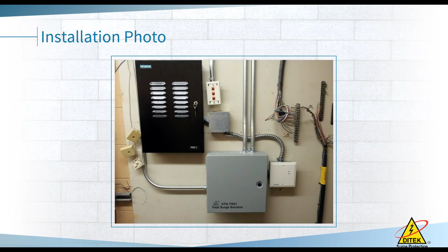I've done a number of site surveys where contractors have run a ground wire from a device like this, and let's say they came out to the left to where this bus bar is, and let's assume that bus bar is a wall. They hit that wall and they make a 90-degree sharp turn down to the bottom. They reference ground at the bottom at the floor. You don't want to make a 90-degree turn on these ground wires.